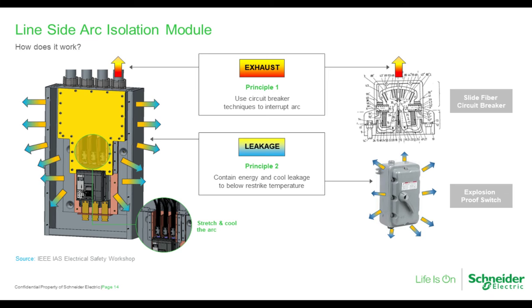And then even if it did, it would be immediately cleared, effectively a belt and suspenders approach. In terms of protecting the user, the cooling effect of the overlap seals, the limited duration of the arc, typically less than 1 cycle, and the evacuation of energy via the exhaust all combine so that the incident energies in the immediate proximity of the user, if there was to be an arc inside the ArcBlok, tend to be very low, much less than 1 calorie per centimeter squared.